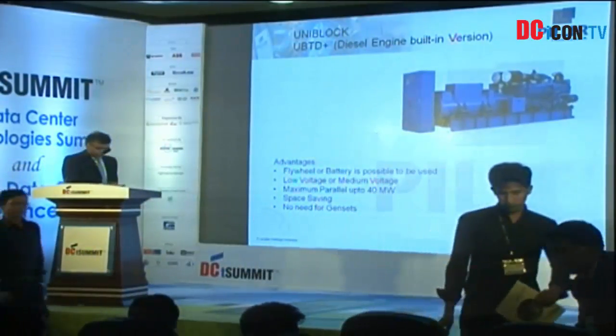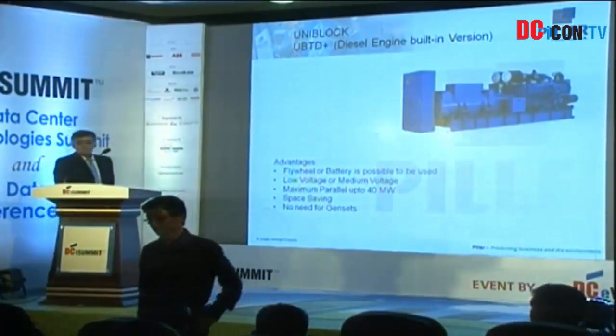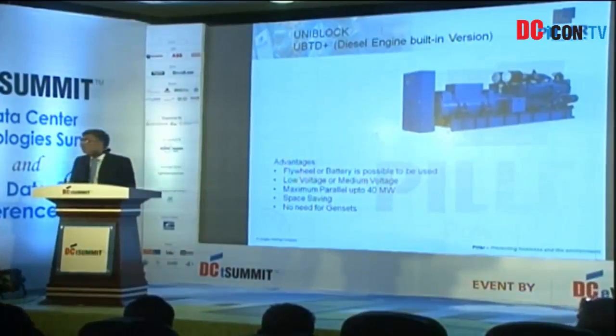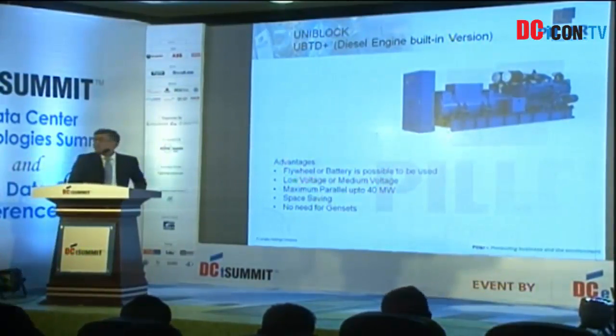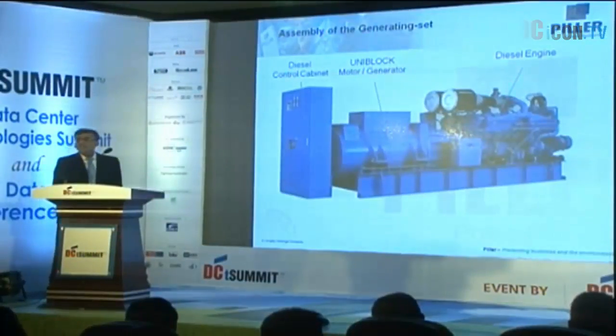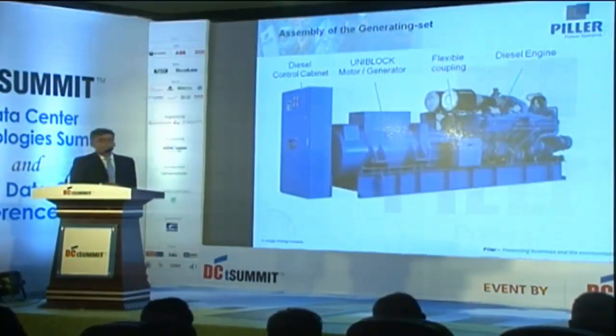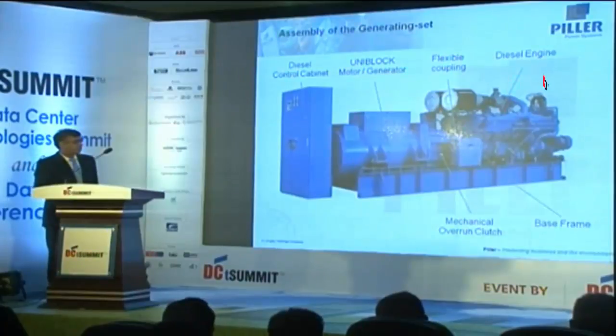The advantages, here again, the flywheel or battery can be used. It can be a low voltage or a medium voltage configuration. You can parallel maximum up to 40 megawatt of UPS. In low voltage UPS you can parallel only up to 4 megawatt of UPS, whereas in medium voltage configuration you can parallel up to 40 megawatt. Space saving and no need for additional gensets. So what are the components here? That's a diesel engine. This is a diesel control cabinet. You have the uniblock, a motor generator, flexible coupling, a mechanical overrun clutch, base frame, and anti-vibration pads.